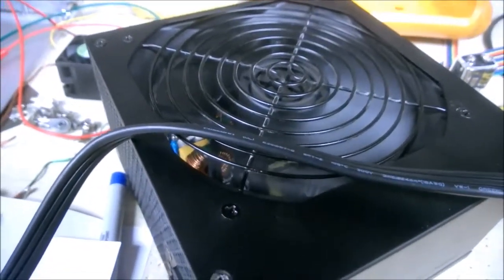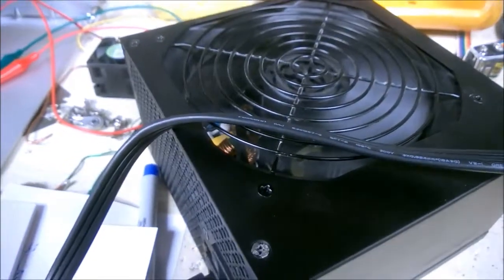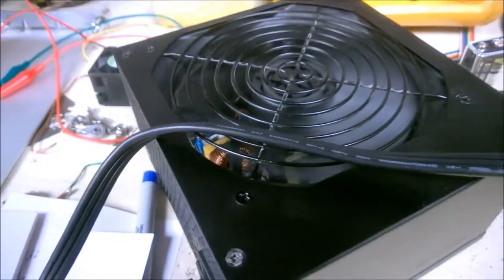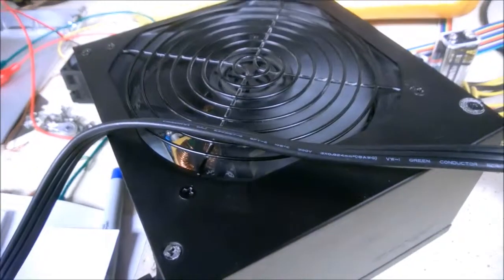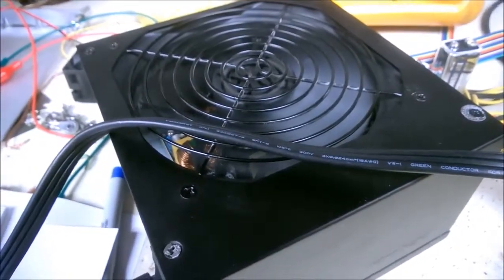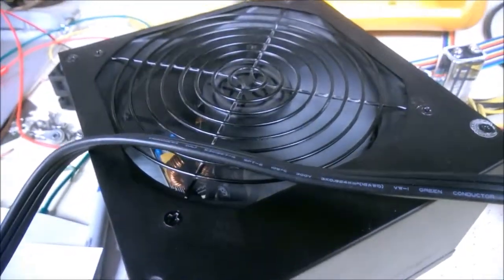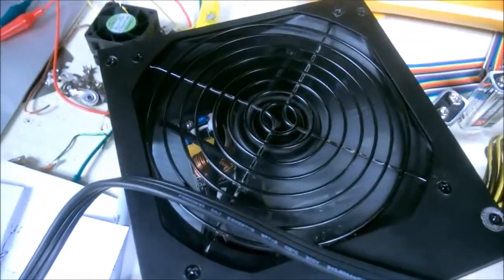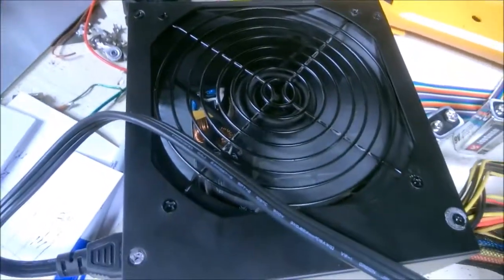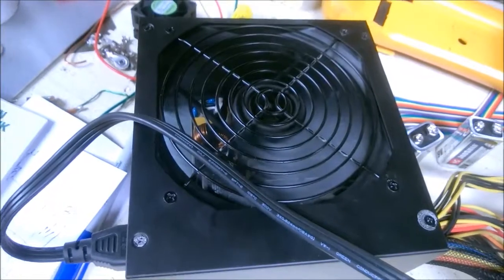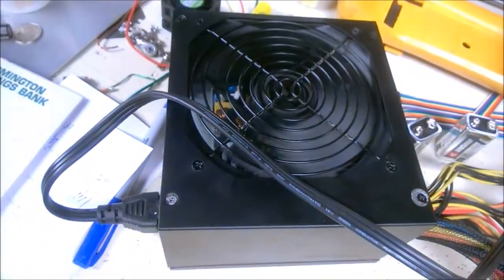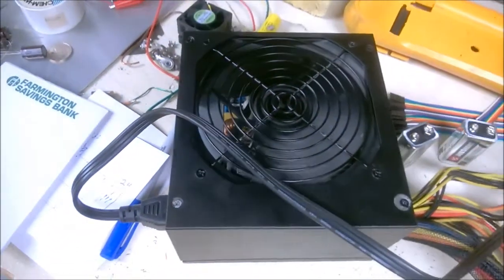There's certainly a number of cases where the power necessary to set fire is well below what's required to set a circuit breaker off. So circuit breakers are great insurance, but they are not the whole story. Maybe that would be something to demonstrate here on the show, as well as the inherent lack of protection on electrical devices, and especially power supplies.